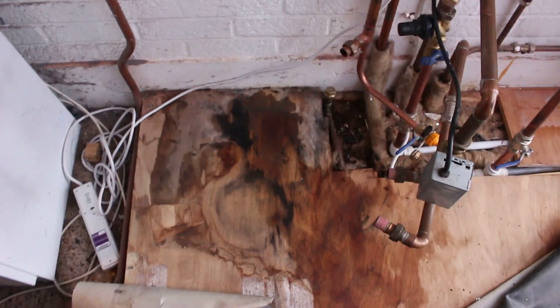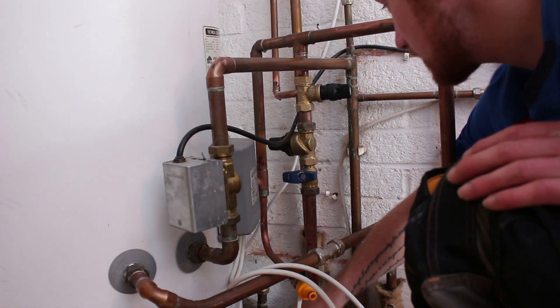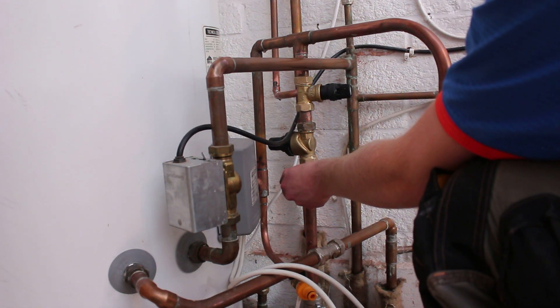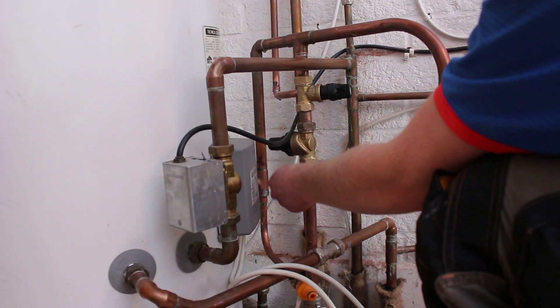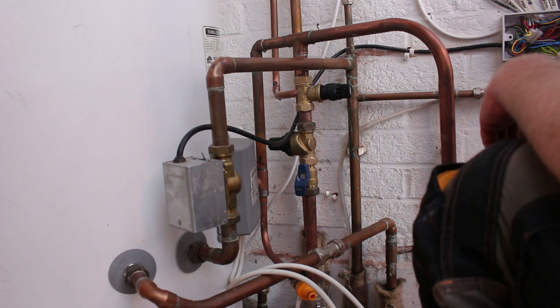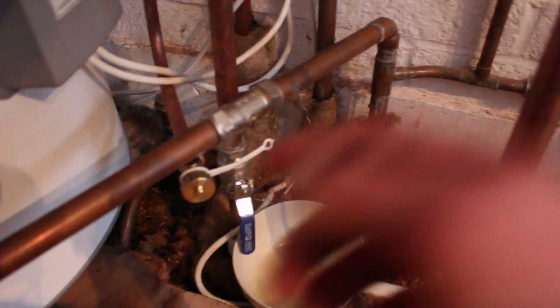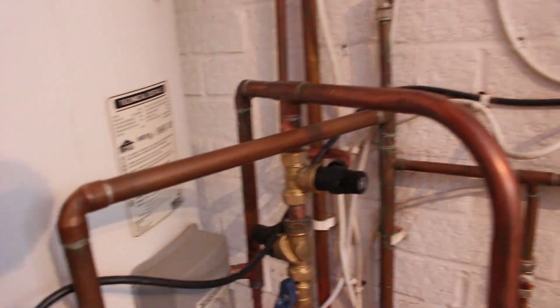I've done all my checks — now it's the moment of truth, time to turn it back on. Looks good so far. The boiler is now on, that's all fixed. The only thing is this isolation valve is leaking slightly, so we'll come back tomorrow and fit another quarter-turn lever valve to sort that. Thank you for watching, I hope you learned something — until next time, keep plumbing.